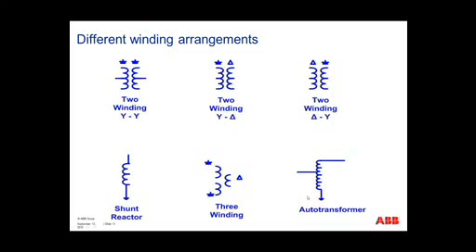And the big difference between an auto transformer, as kind of shown in this picture, is that not only is it electrically coupled, but it's magnetically coupled as well from the high side to the low side. Auto transformers are typically used in transmission systems, but you can actually manipulate the voltage in respect to the low side voltage by the placement of this load tap changer in this auto transformer.